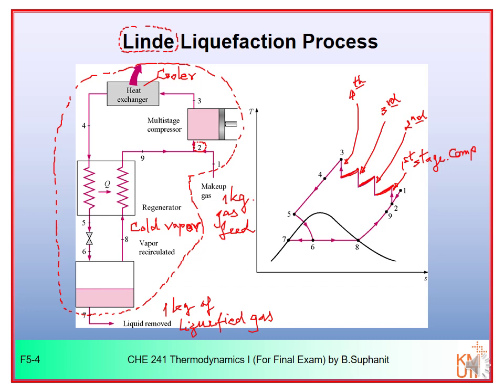After exiting the last stage compression, the gas is cooled in the cooler (three to four). Then four to five is the regenerator — you cool the gas further to a lower temperature by exchanging heat with the cold vapor from eight to nine. So four to five transfers heat to eight to nine in the regenerator.